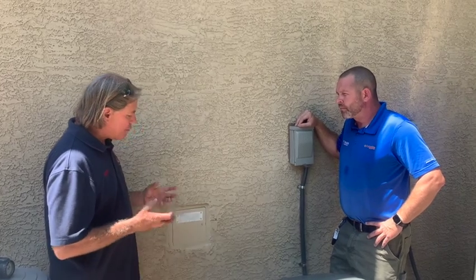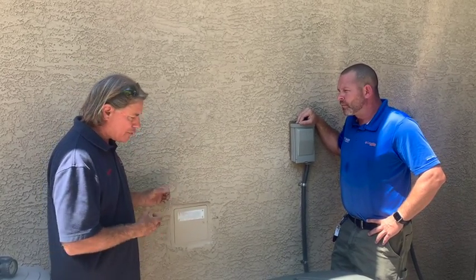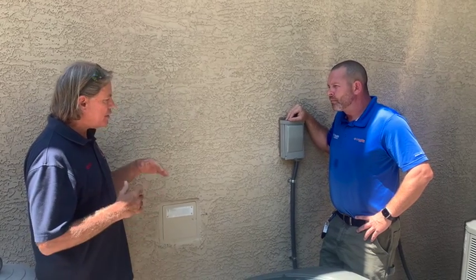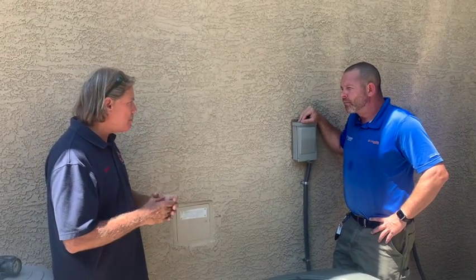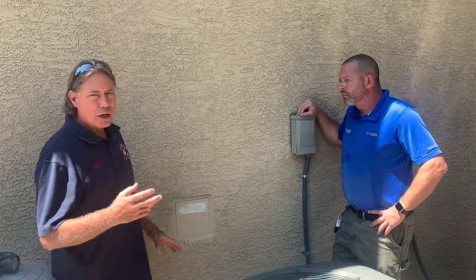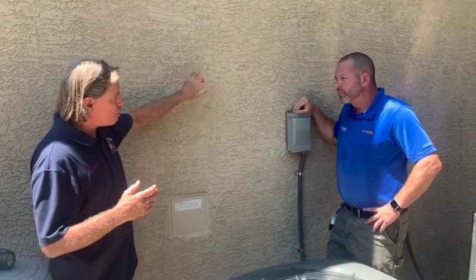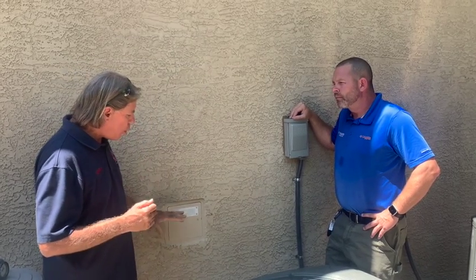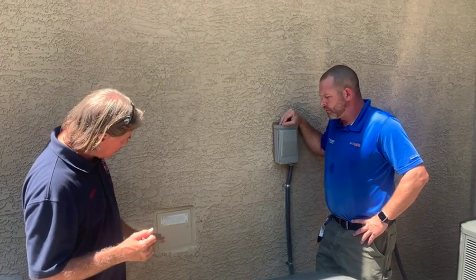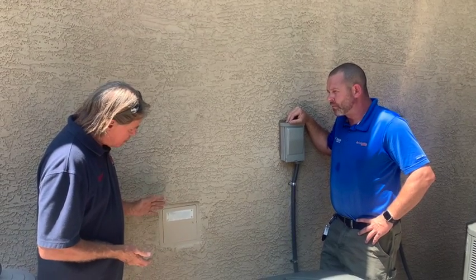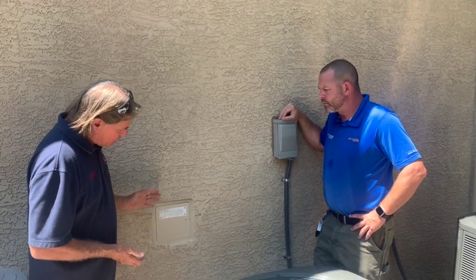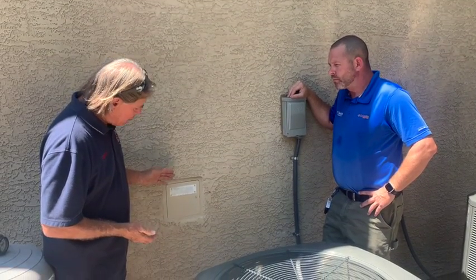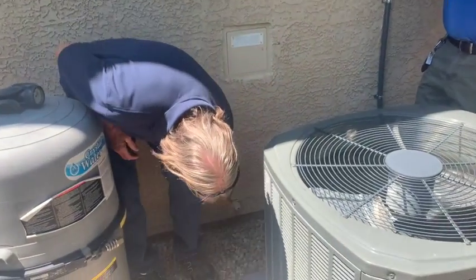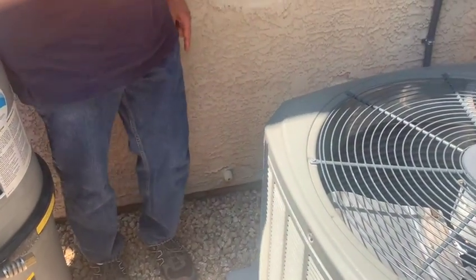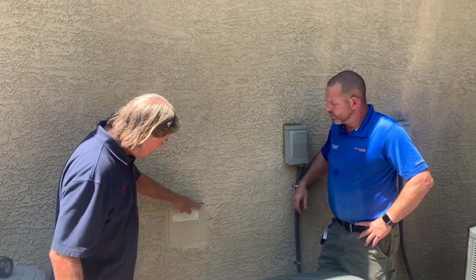And the other is when they first install the system, it's required for us to flow the system and see if it is installed properly with the right size piping, the right amount of water pressure flowing, with the residual flow pressure that we look at on the gauge over there with the system flowing. This is a somewhat typical inspector's test that we would see in a residential setting. They have piped it. Here's the outlet for the inspector's test. It's reduced to a 7/16 orifice. Therefore, it's emulating a fire sprinkler going off or deploying.